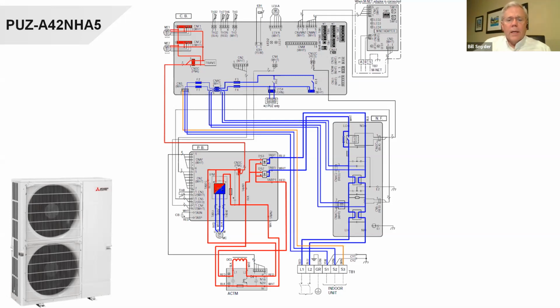And it actually helps smooth out that voltage circuit. Sometimes this reactor is on the AC circuit side, and sometimes it's on the DC side. But it's doing the same thing. It's basically smoothing out the voltage. And the power going in and the power coming out of that, if you were to measure it, you should not see much, if any, of a voltage drop.